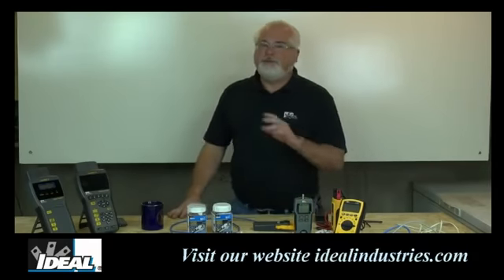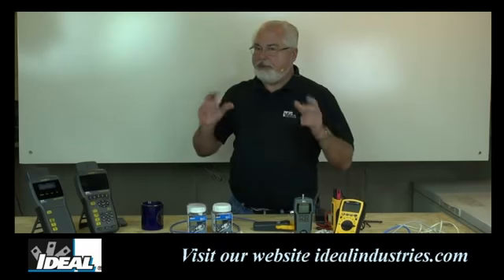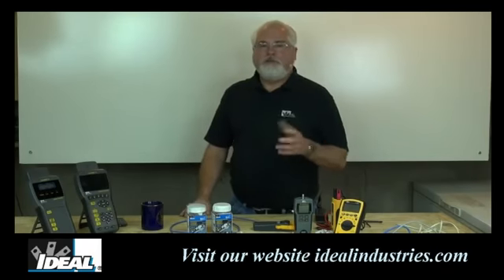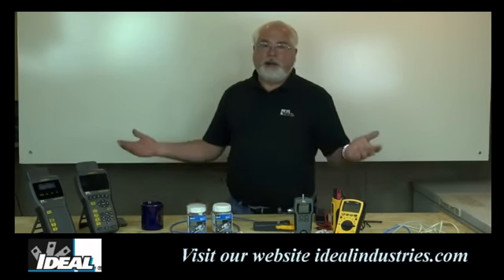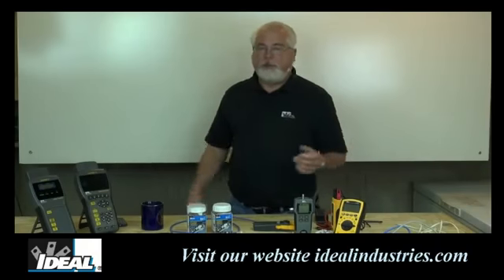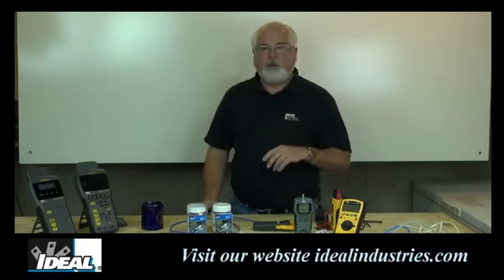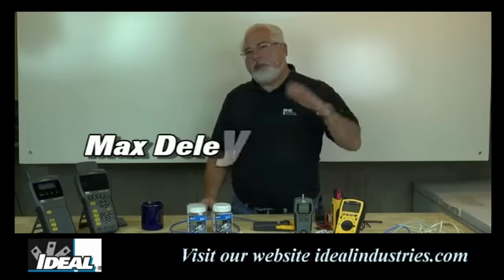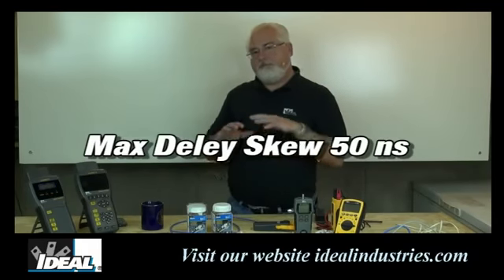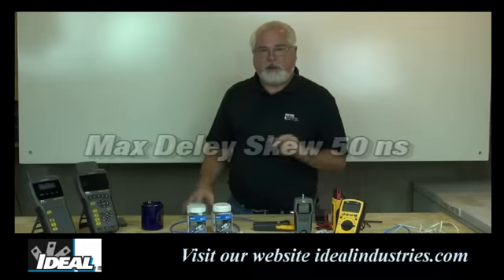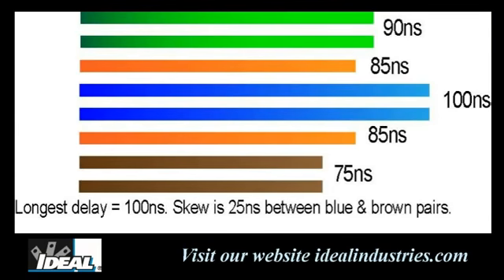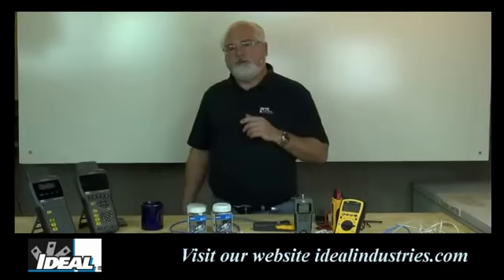Now, the delay skew is the difference between the four pairs because, again, keep in mind each pair is twisted at a different rate. In general, I'm going to tell you the blue pair is twisted the most and the brown pair generally the least, although not always, but a lot of times we'll look at those pairs to see what that skew might be. And the industry allows us a maximum of 50 nanoseconds for things to be working, okay? So here we're looking at a cable with the blue pair, which has a delay of roughly 100 nanoseconds. The brown pair is at 75 nanoseconds, and of course the difference there is 25 nanoseconds, which is within the maximum set of 50 for the industry, okay?